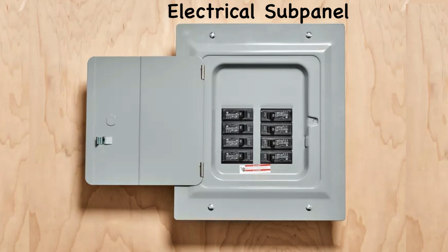Subpanels are typically 60 to 100 amps, and often have branch circuits serving a specific area of the house, such as a kitchen. They have their own main breaker, which is fed by the main panel. If your home has a subpanel, there will be a double pole breaker in the main panel that has the same amp rating as the main breaker in the subpanel. Subpanels don't always have main breakers, they may have lugs only, which allow the feeder wires to be connected. Because the subpanel is fed by the main panel, you do not add the subpanel's amp rating to the household total, use the main panel's amperage only.